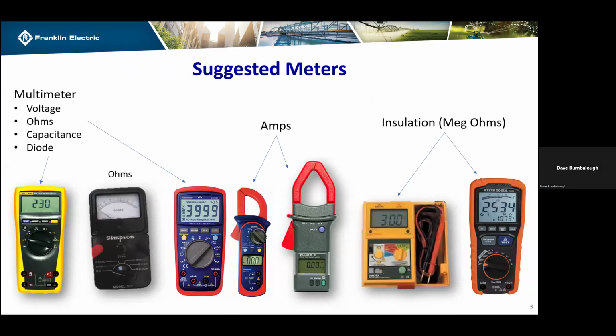When it comes to your meter selections, the common meters you're going to have are a multimeter, usually some kind of amp meter and/or fork style device to check your amperage and/or frequency, and then a way of checking the wire to make sure that you don't have any ground fault issues, because that in itself can contribute to leakage voltage or stray voltage issues. This instrument is designed to look for those pinholes. If voltage is getting out, this meter is going to find it. I'm going to walk you through that.